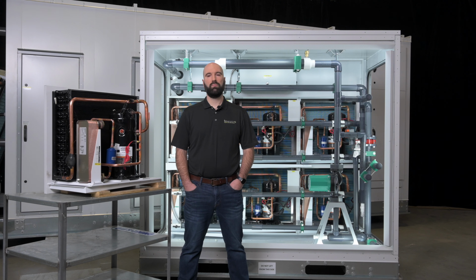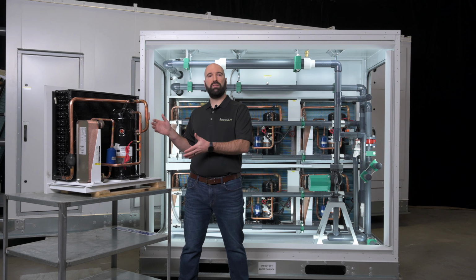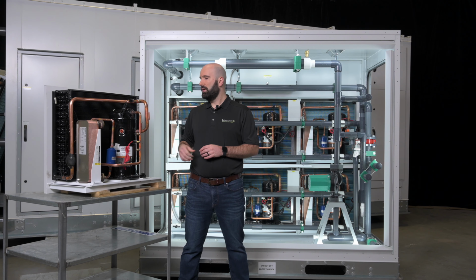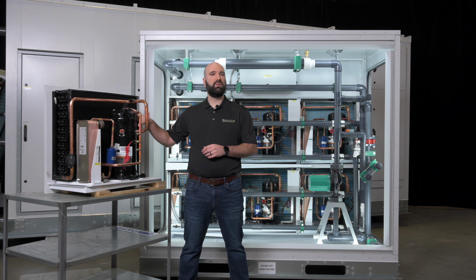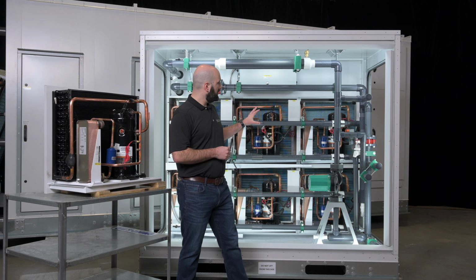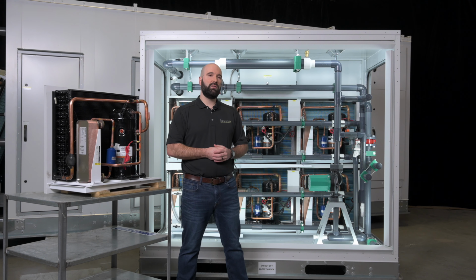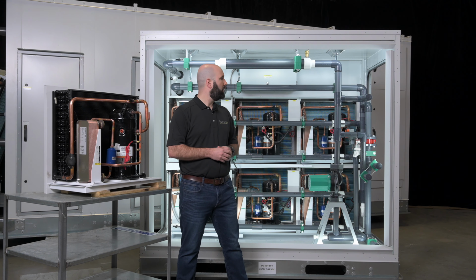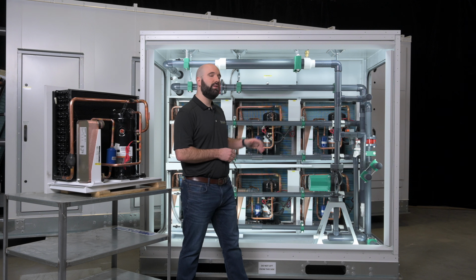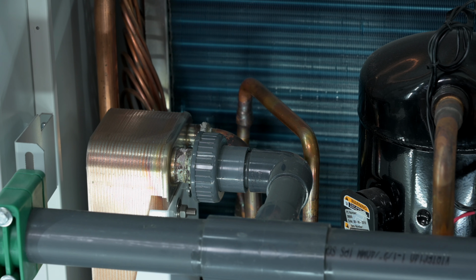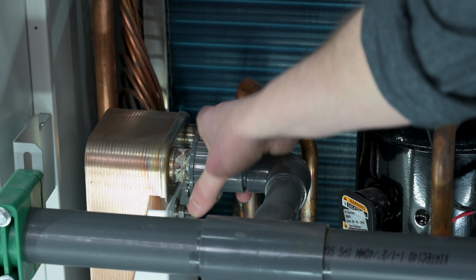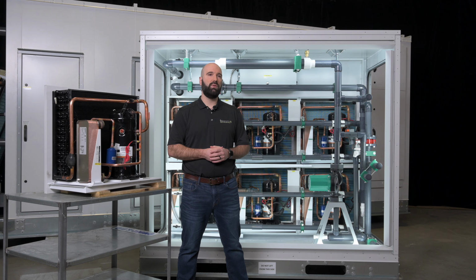So to my right here you see one of the individual compressor pods that makes up all of our compressor wall units. These pods are available in 2 sizes. They're physically the same dimension, but just with a different compressor capacity. And again, that 6.3 or 7.6 ton size that we multiply out to achieve the breadth of product line that we have. Here's a typical configuration of how they're put together. This is a 6-pod show wall, but what we've got here are 6.3 ton pods that make up our 36-ton compressor wall. Each of those pods is electrically independent and has an individual waterside disconnect that allows you to remove it from the loop without draining the hydronic loop and allows the reheat assembly to work properly.